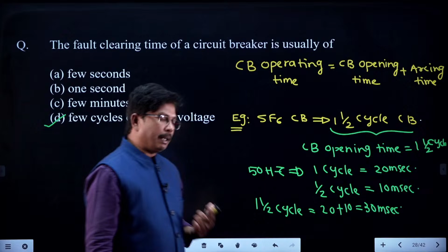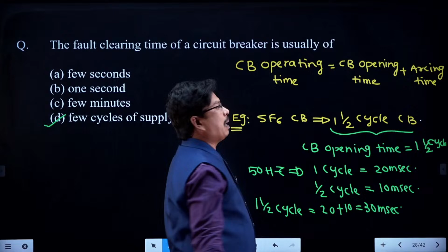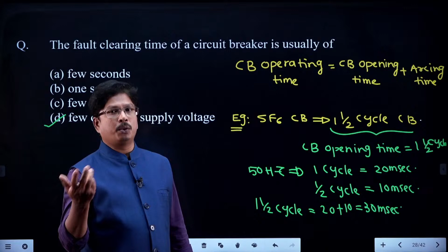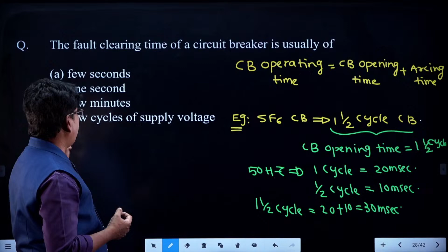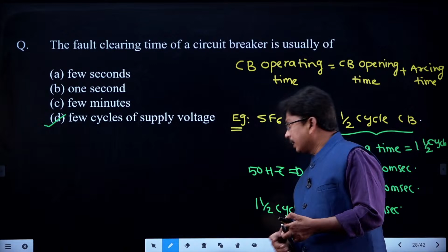So, the CB opening time. Along with that, some arcing time will be there, and it will be less than the opening time. So the highest amount of time will be the opening time, and the least amount of time will be the arcing time. Suppose if it is 30 milliseconds, the arcing time will be some 10 milliseconds, then the CB operating time will be nearly 40 milliseconds. So that CB operating time is 2 cycles, it is a 2 cycle circuit breaker, right. The CB has an operating time of 2 cycles, like that you can mention. That is why the fault clearing time of a circuit breaker is always mentioned in a few cycles of the supply voltage. Got it right? Right. Lightning arrestor should be located away from the circuit breaker, near the circuit breaker, near the transformer, or away from the transformer. What should be the answer?